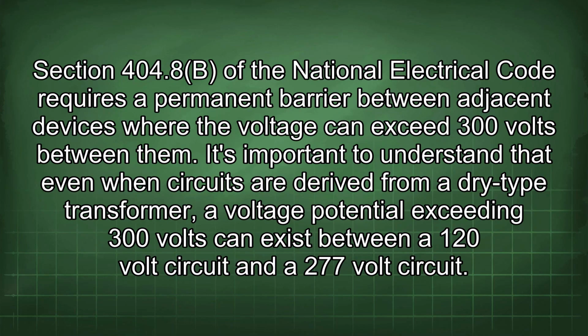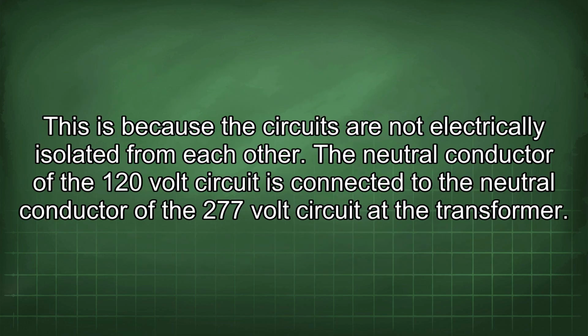Section 404.8(B) of the National Electrical Code requires a permanent barrier between adjacent devices where the voltage can exceed 300 volts between them. It's important to understand that even when circuits are derived from a dry-type transformer, a voltage potential exceeding 300 volts can exist between a 120-volt circuit and a 277-volt circuit. This is because the circuits are not electrically isolated from each other.